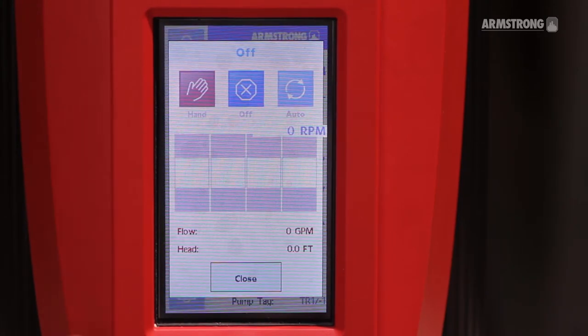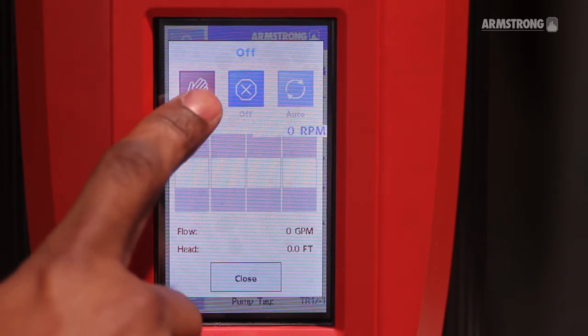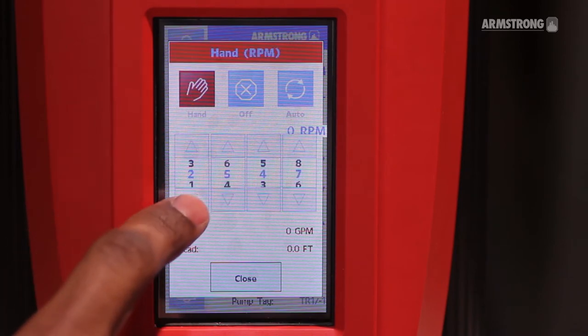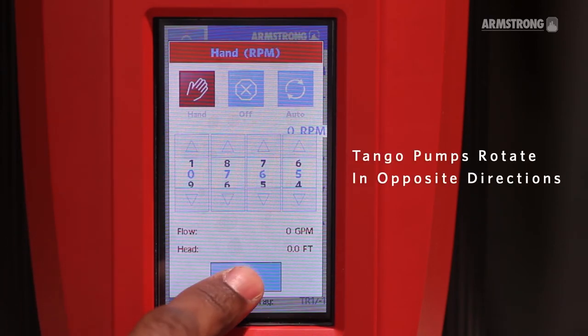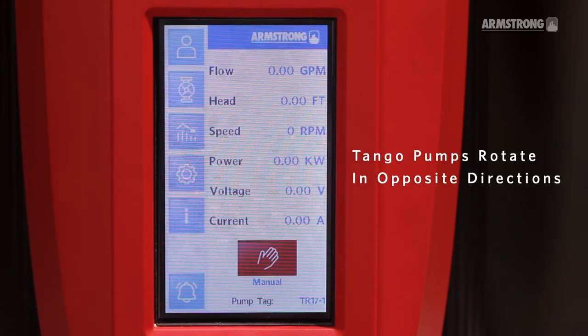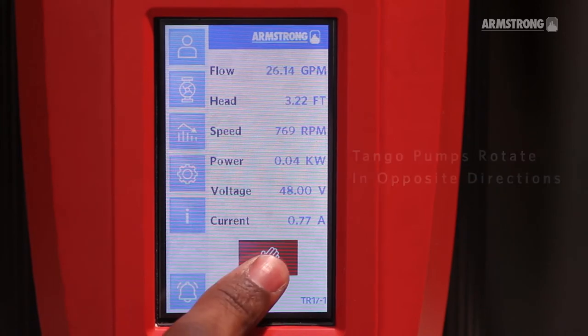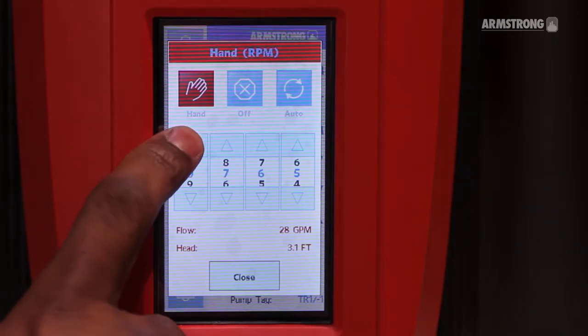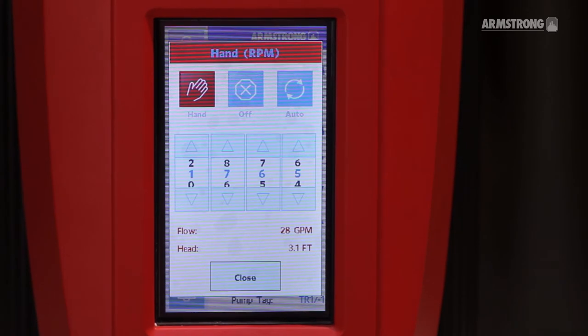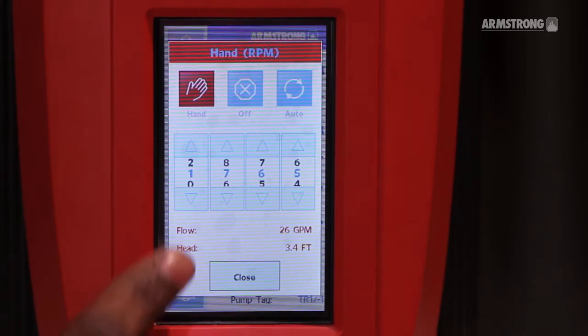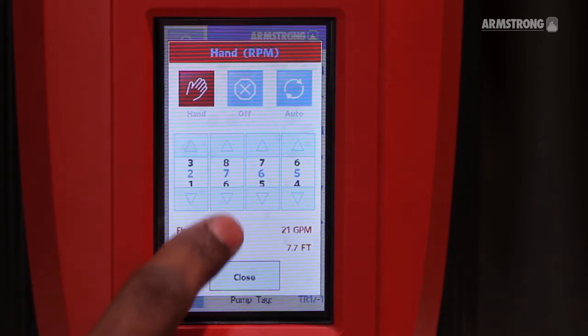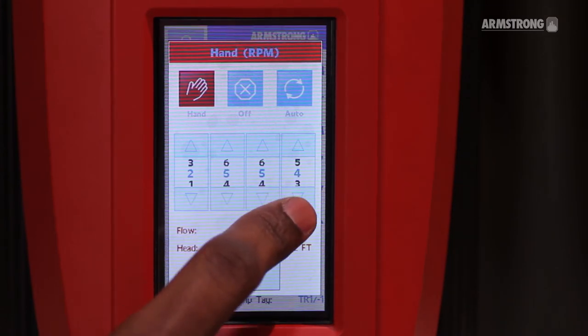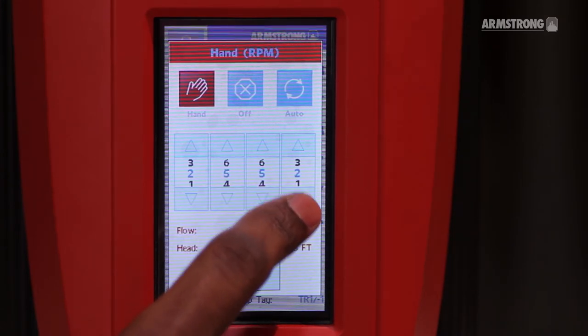Place the pump in hand and confirm rotation by setting it to minimum speed. With the pump in hand, ramp up or down until you reach the design or desired flow. We are looking for 95 GPM.